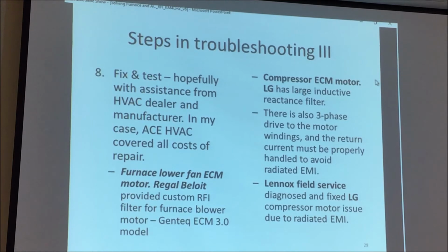The Lennox field service engineer found there was a problem with the LG compressor motor, but it was not the fault of the motor. LG was less cooperative than Regal Beloit. They said they have a large inductive reactance filter, and that's the end of the story. Nonetheless, we are still getting interference.